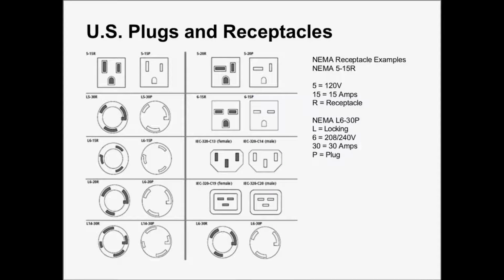Now, what I'd like to talk about is there's really two different ways to install a UPS system. Essentially, you can do plugs and receptacles, or you can do hardwired. So we're going to talk about plugs and receptacles here real quick. It follows the NEMA convention, which is the National Electrical Manufacturers Association. It's a code, and for example, a NEMA 5-15, which is what is in most people's homes, the 5 stands for 120 volts, the 15 is for 15 amps, and the R is for receptacle. And so that's this plug here, plug and receptacle.